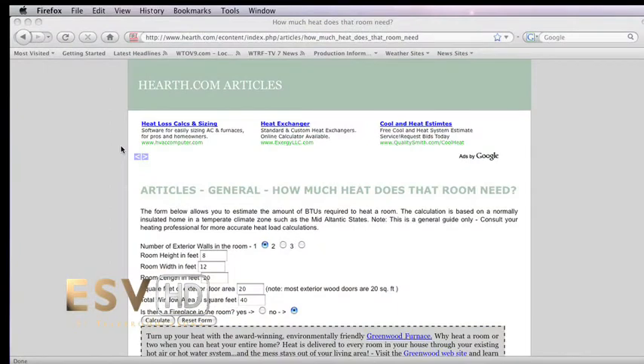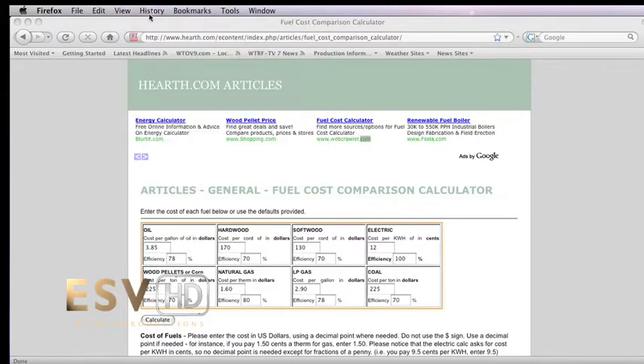But more than that, it's just simply the cost per year. There is a way to calculate how many dollars it takes to heat your house with geothermal or fuel oil or propane or natural gas. We know how many BTUs is in a gallon of fuel oil, propane, cubic foot of natural gas. If we know the efficiency of the appliance and the cost per gallon or cubic foot, we just come up with the national standard for comparison, and that's cost per million BTUs.